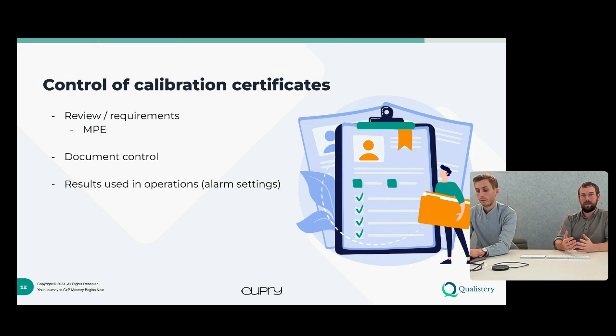And then secondly, again back to documentation, having control over your calibration certificates. Where do you store those calibration certificates? Are they stored so that they're easily retrievable and they eliminate risk of errors when retrieving those? So do you risk retrieving an old calibration certificate, for example, or one for a different unit? So really having all those calibration certificates in one place is one of the key things I would go for, at least. Because it's easy also in the audit to just get it all very fast.